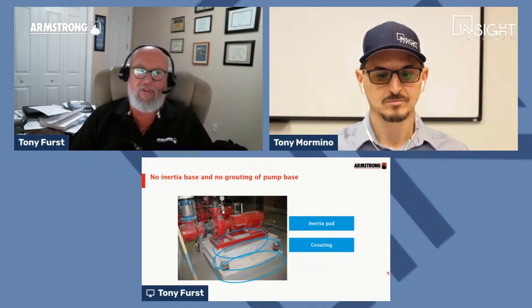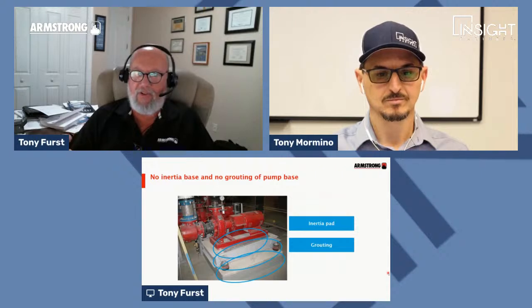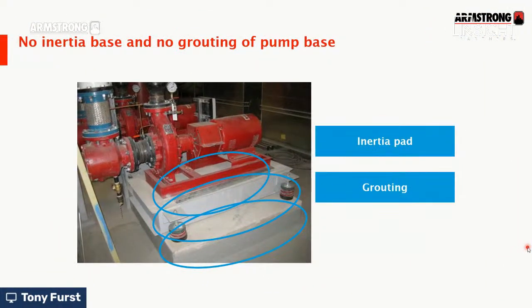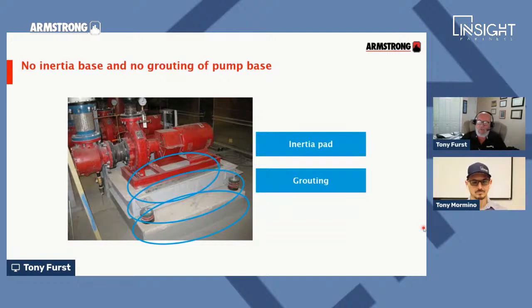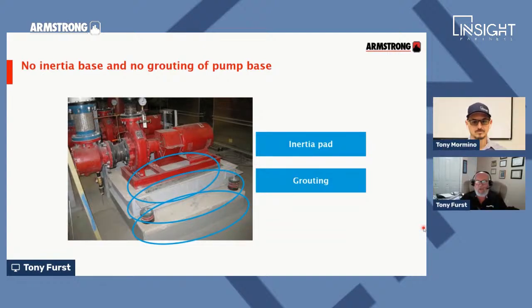The first two things we're going to talk about is you don't need an inertia base and you don't need to grout the pump base, because there is no pump base. You don't need an inertia base because the pump is fully supported by the piping, so there's nothing underneath it. You don't need a housekeeping pad, you don't need any of that. So there's a huge cost saving advantage to getting rid of all that stuff underneath the pump.